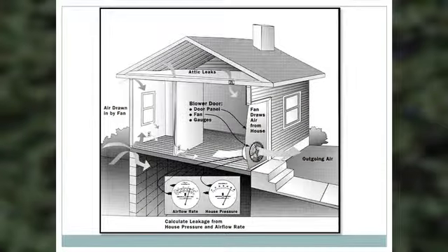Now, because we are pulling air out of the house, all the air going out of the house is going out through the fan, which means that whether you're down low or up high, we're pulling air in through every spot in your house that leaks air. We can then, either using our IR gun, tracer smoke, or our calibrated hand, go around the house and detect air leaks. That's the value of our blower door. And we'll find those air leaks at rim joists, at the windows, through can lights, and, believe it or not, through outlets and light switches.